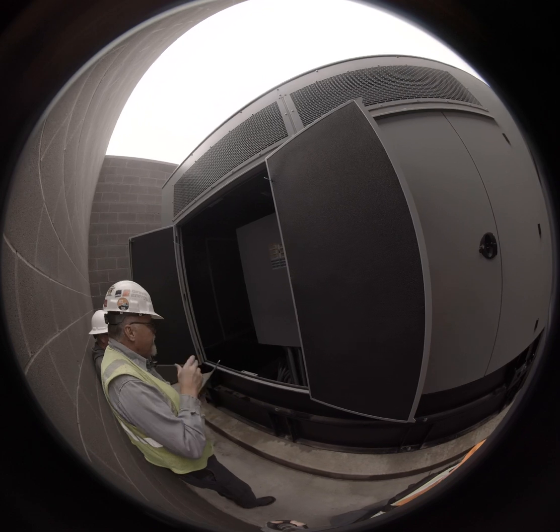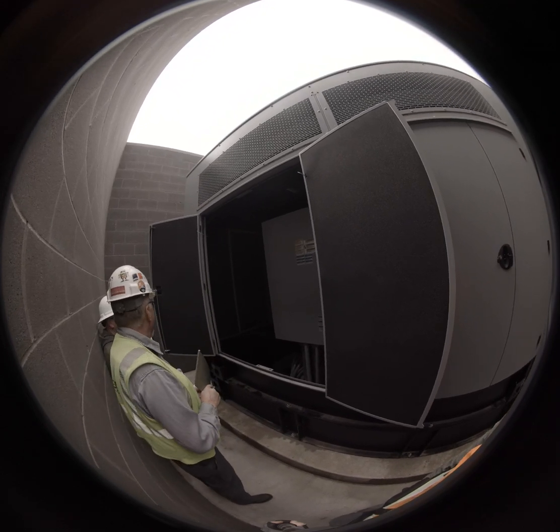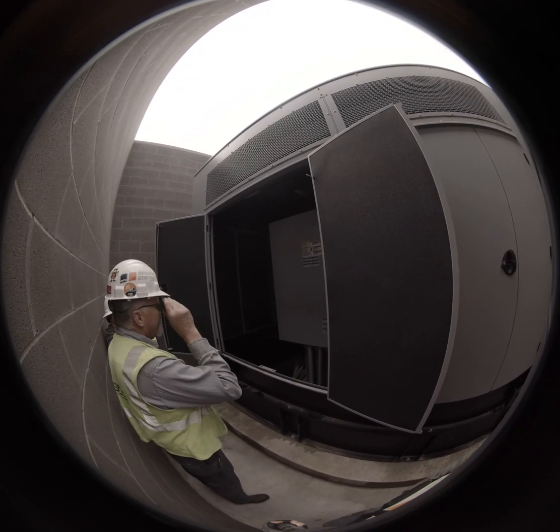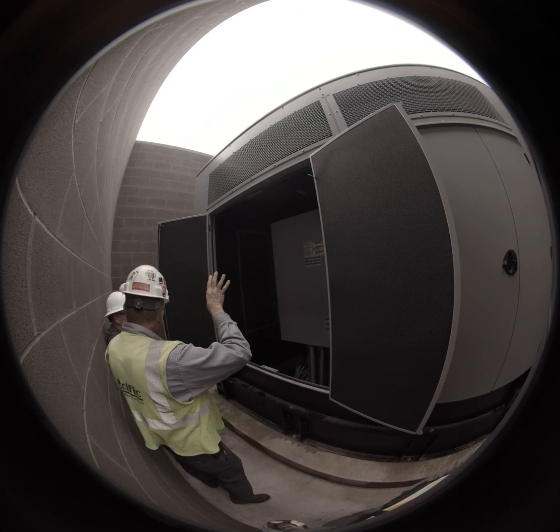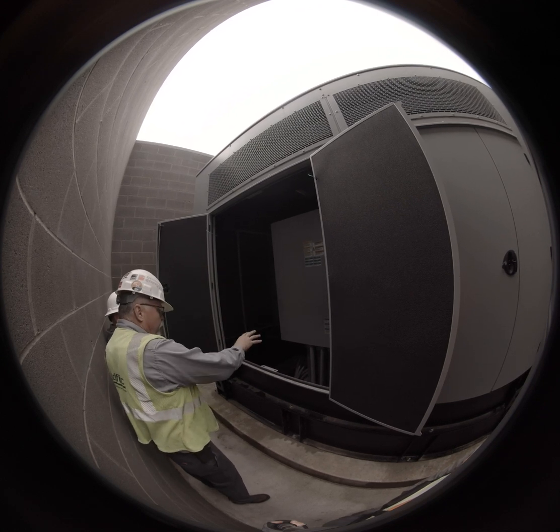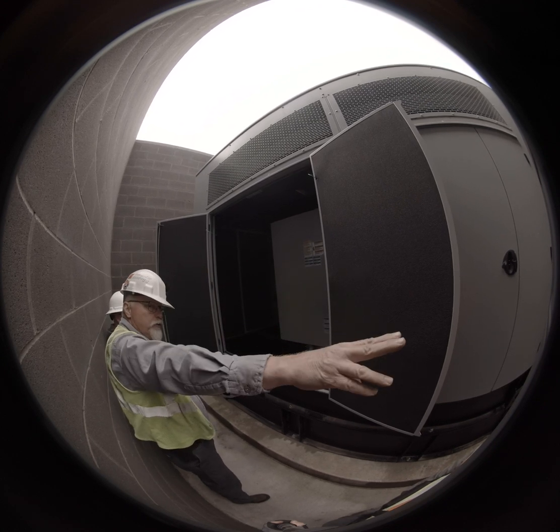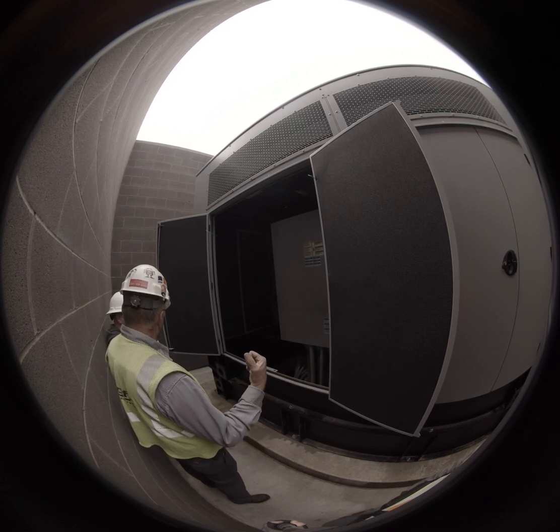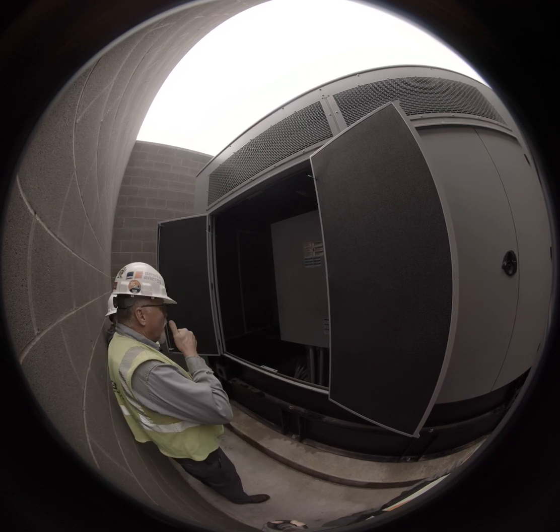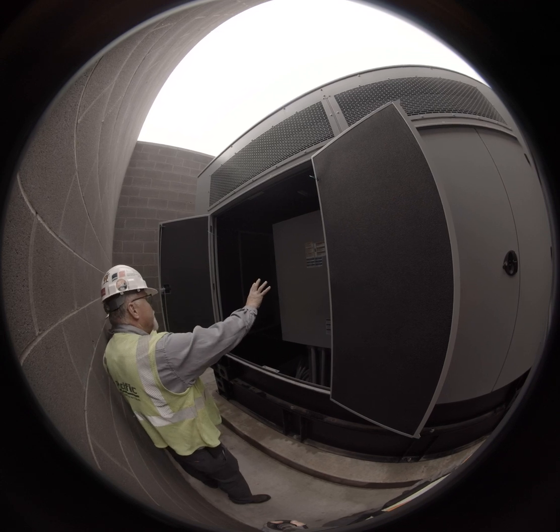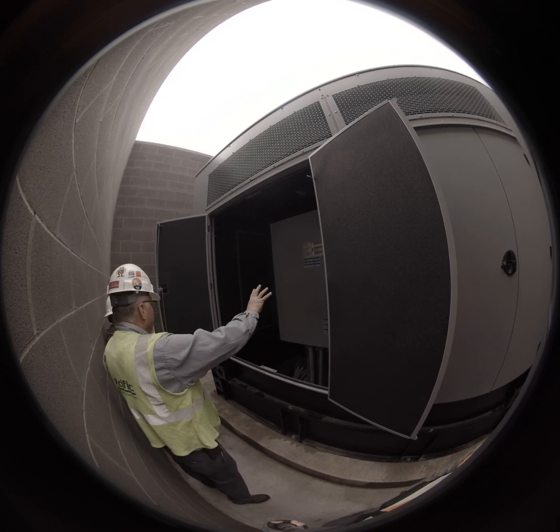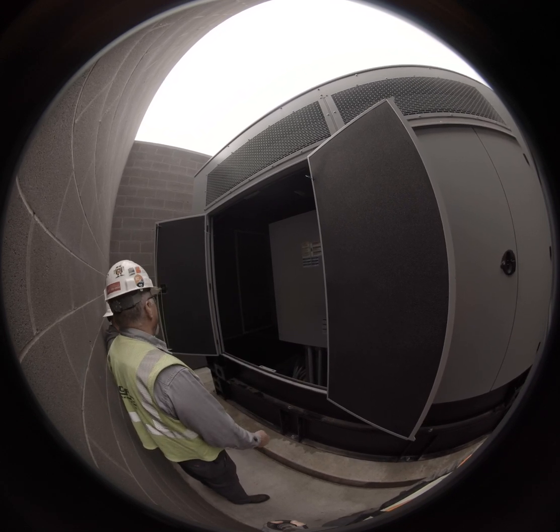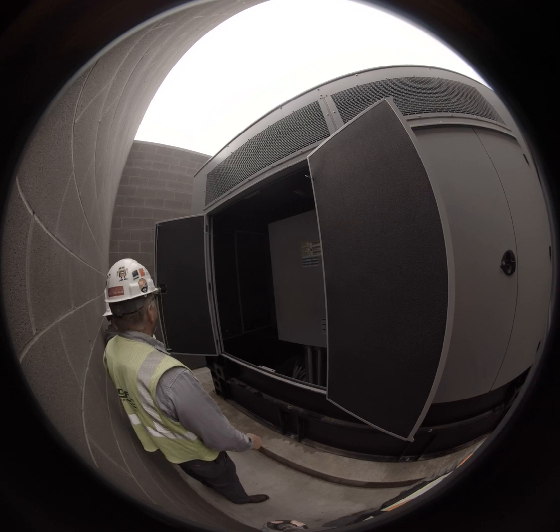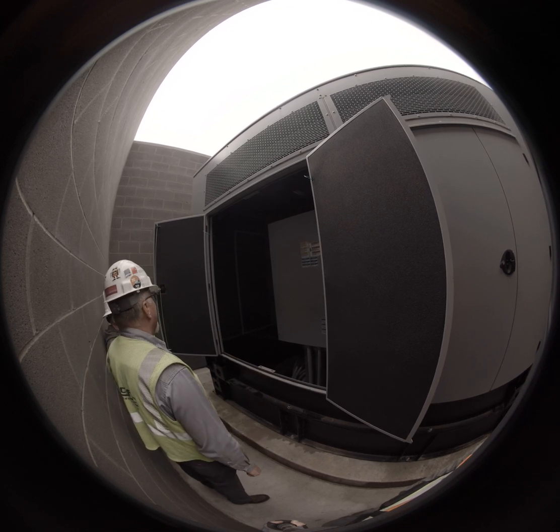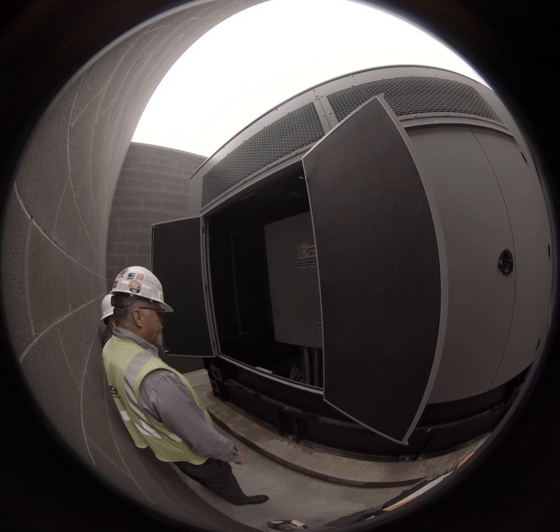So, this generator set does not have an onboard circuit breaker. Inside this here is just connection points for the conductors going over to the tap box, which sits in front of the engine. So inside here, this really should never have to come off unless you've got a company coming in to do IR scanning or something like that, and then they will have their own specifics on it.